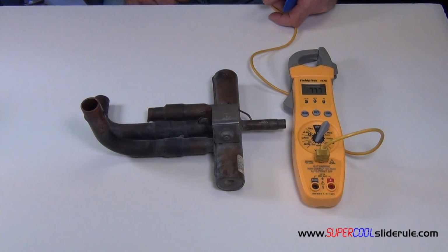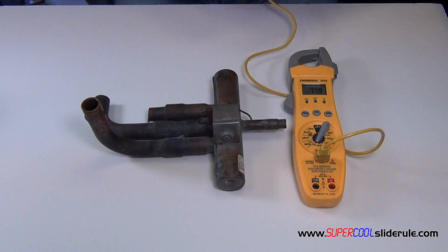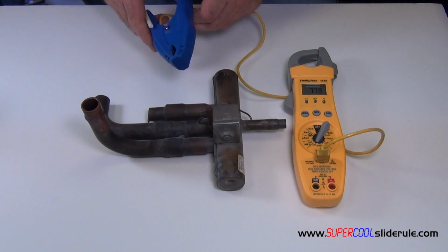In this tutorial we will check the operation of a reversing valve. A reversing valve changes the flow of refrigerant in a heat pump application. The way we test this is with a temperature clamp.